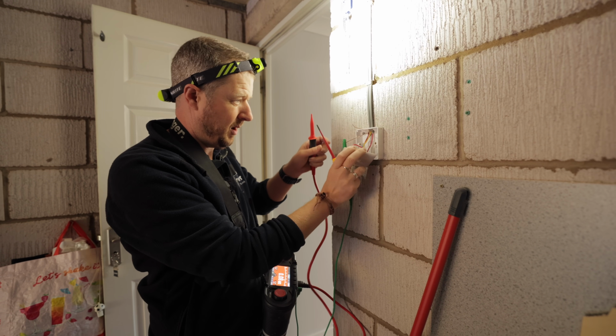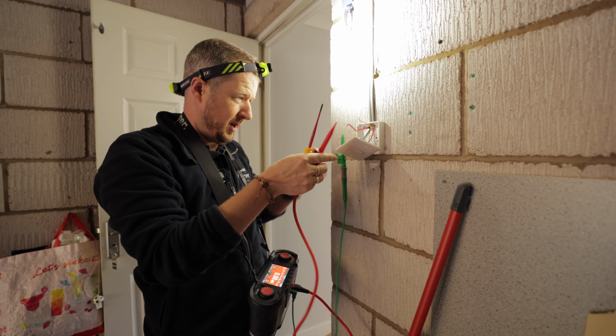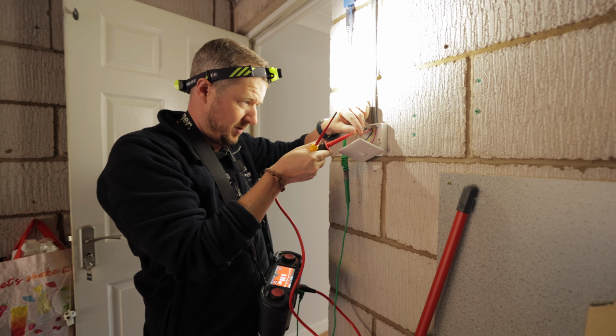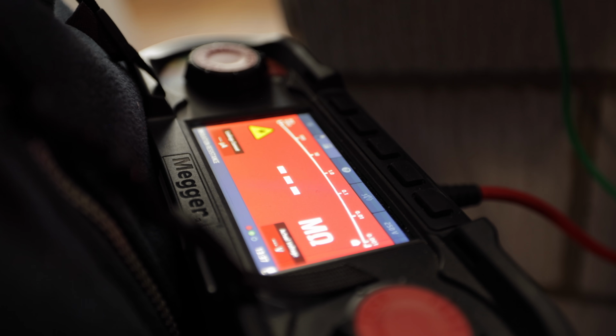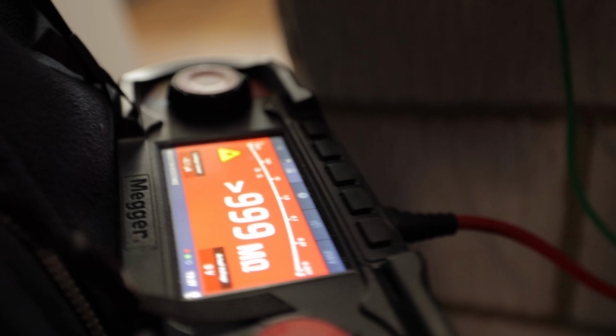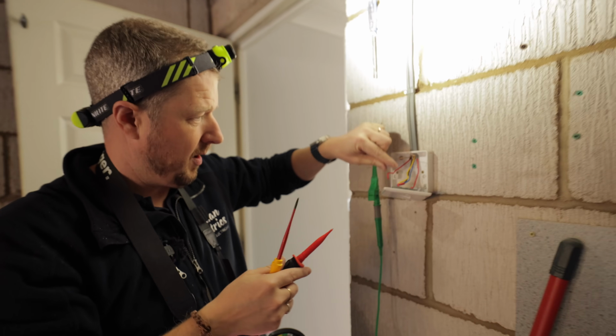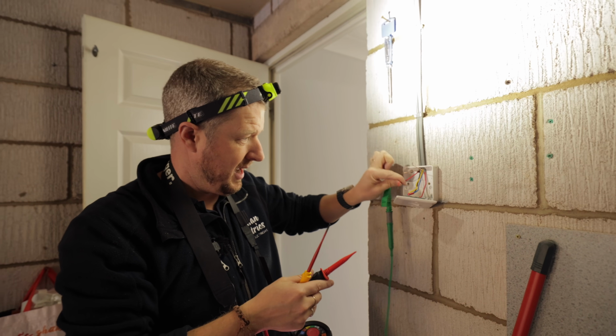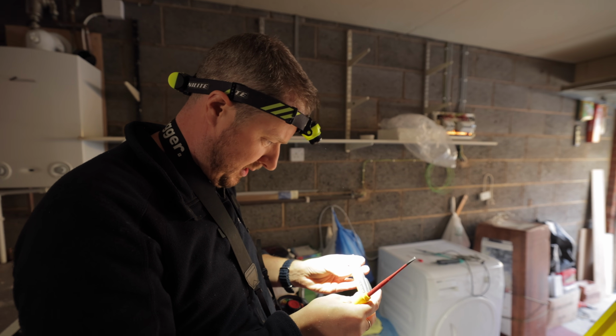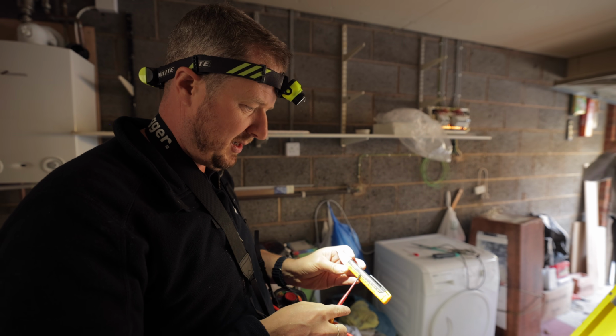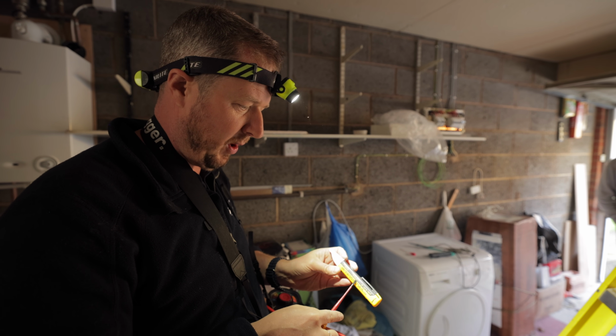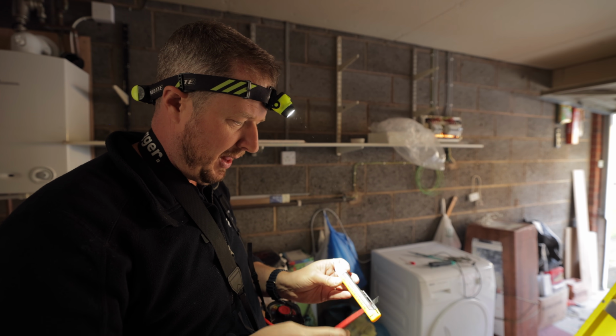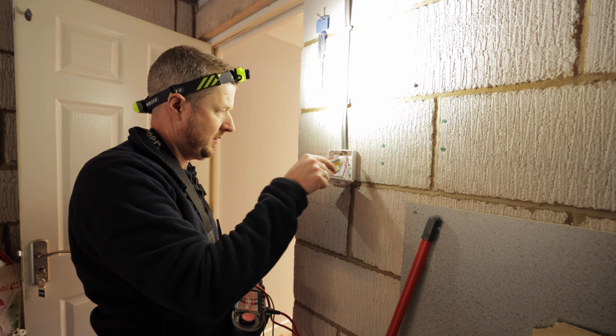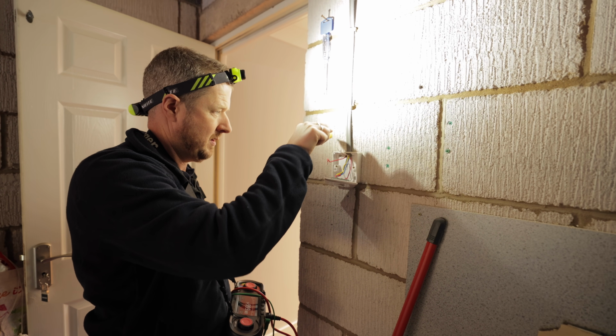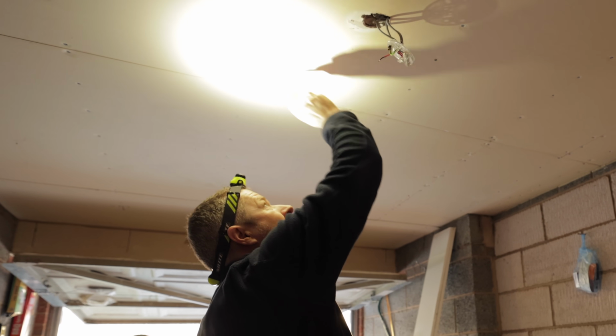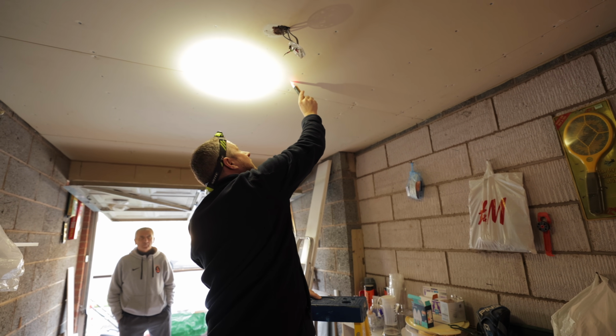Yeah, we've got very low insulation resistance here between the permanent live coming down to this switch and earth. This one's all clear, right? So everything is all clear apart from this permanent live. Right, let's get scientific for a second. These voltage testers, the sensitivity range is 90 to 1000 volts AC. That means that this is only going to kick off if there's more than 90 volts present. So that means there's 90 volts present on this ceiling when it's going off.